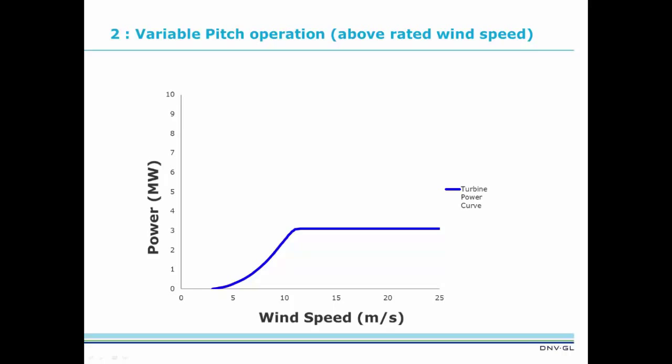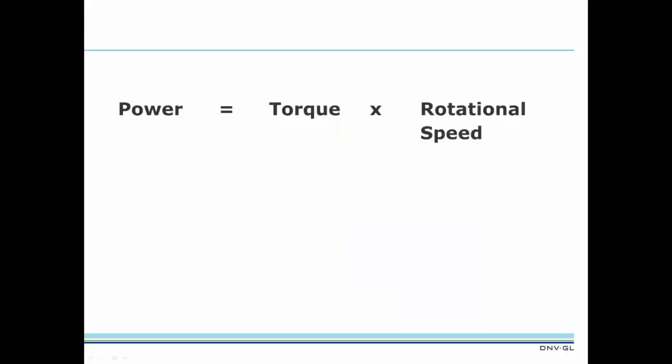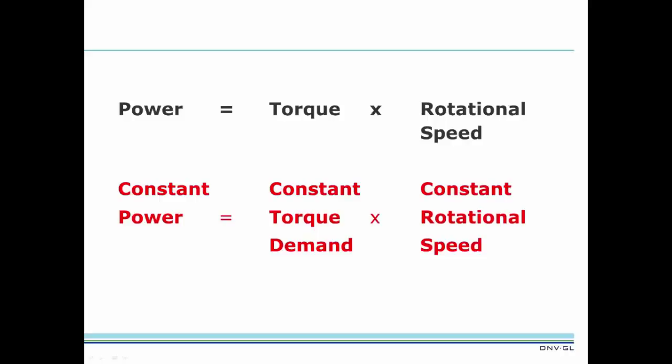Now let's look at what happens for wind speeds above rated. Here, the aim is to generate constant power output from wind of increasing energy. So how is this done? Power equals torque times rotational speed. Constant power is obtained with constant torque demand and constant rotational speed. It's easy for the turbine control system to set a constant torque demand. The challenge is to hold the rotor speed constant as well.